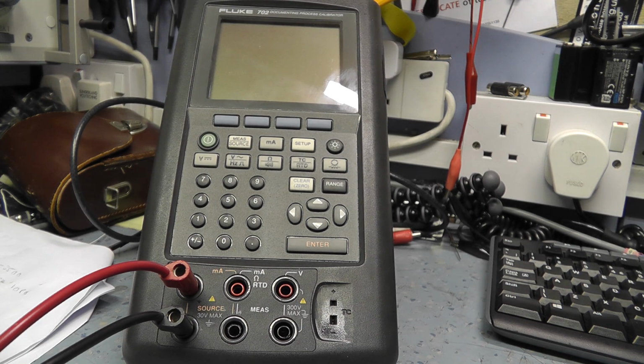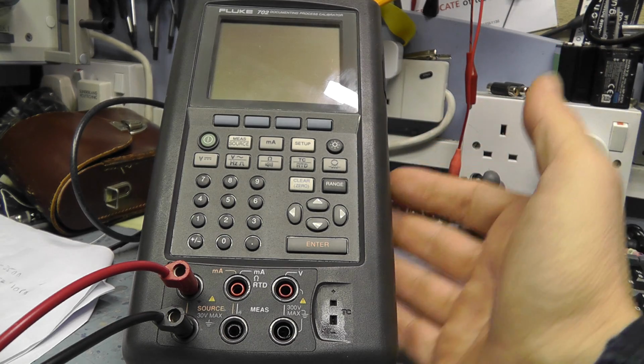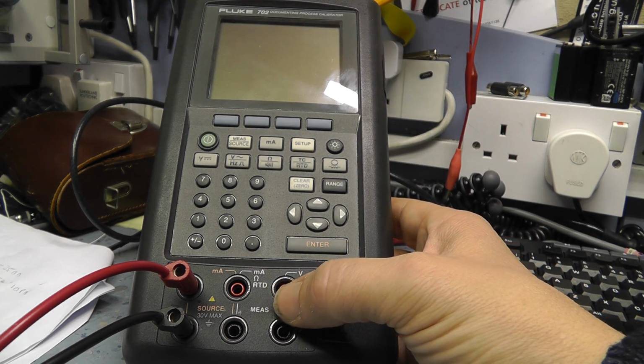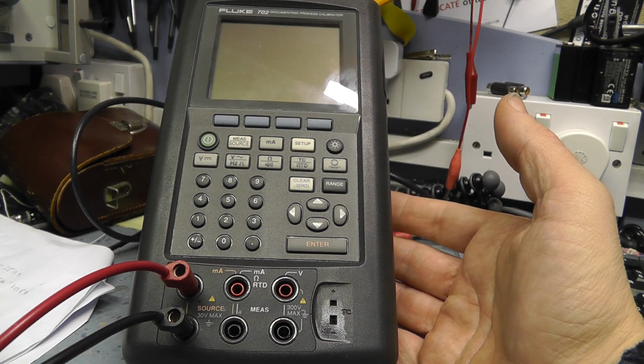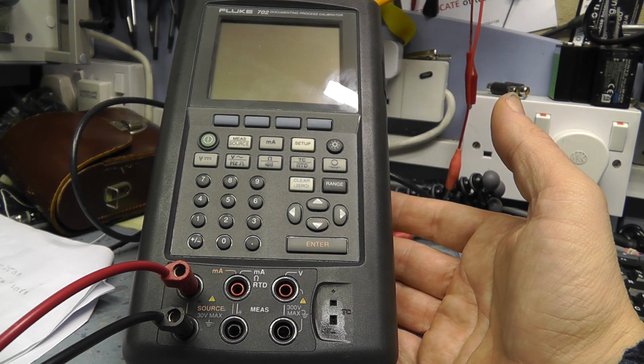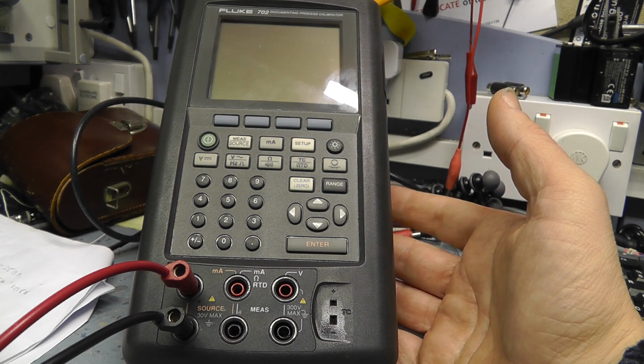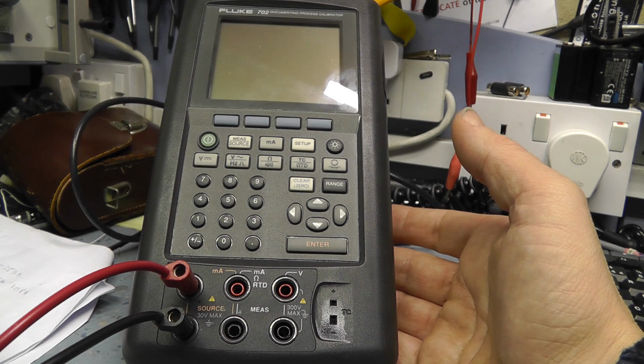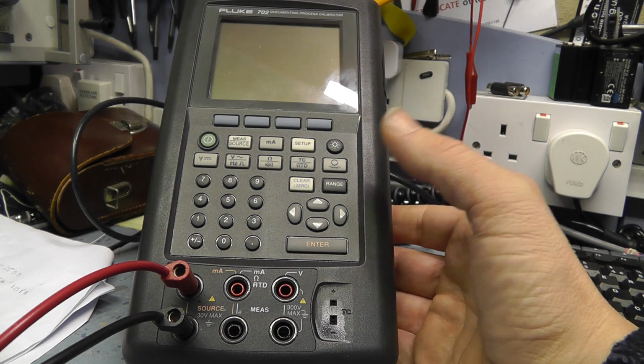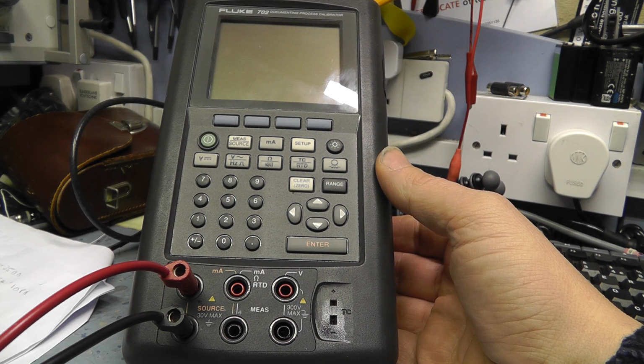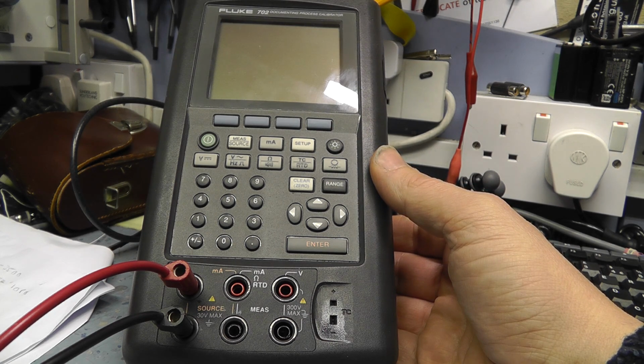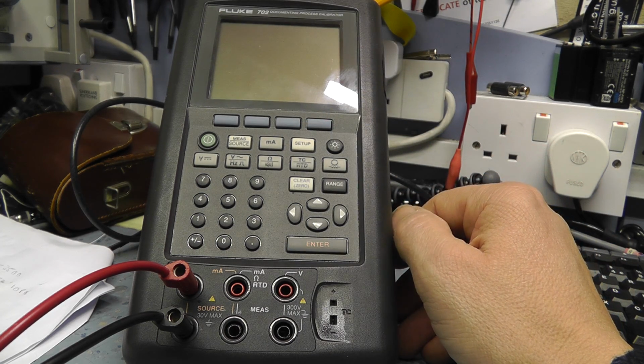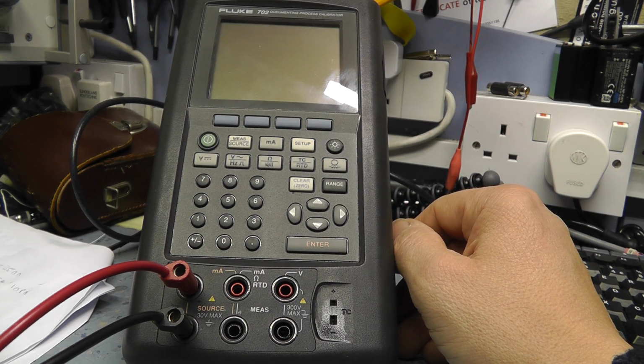So just to quickly run through what I understand of it so far. It's got the ability to log results, so it's like an inbuilt data logger, but it's also a voltmeter and ammeter. It's a bit limited on what it will do as a DVM or multimeter, limited to a fairly low voltage, I think about 250 volts maximum, though I need to check on that. It will source voltage and current, I think voltage up to about 11 volts and current up to about 20 milliamps. It'll also source a resistance, which is nice for calibrating meters and things like that.